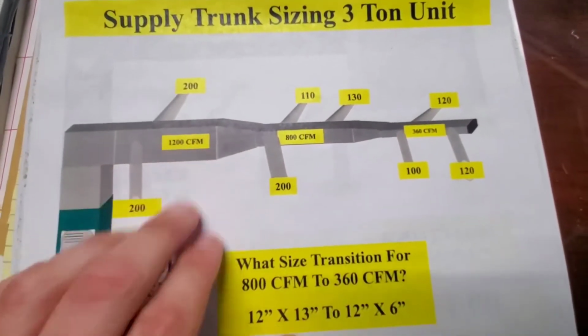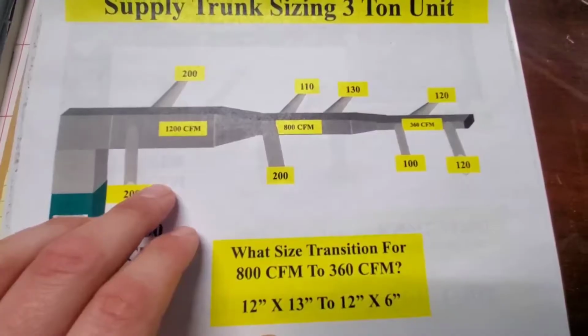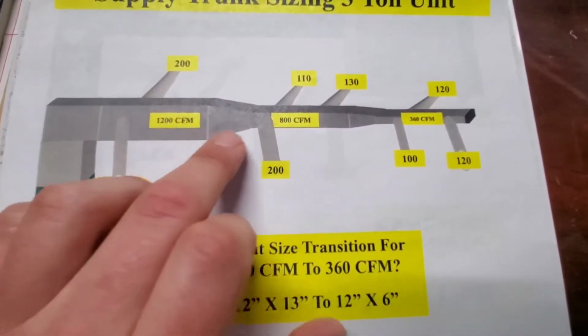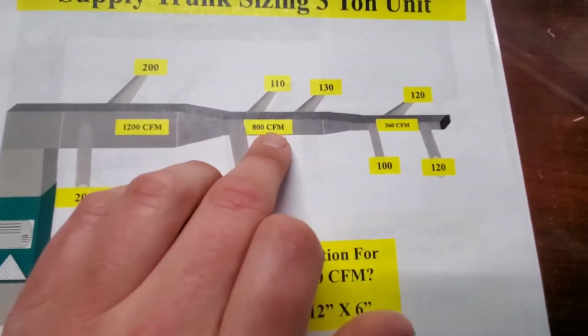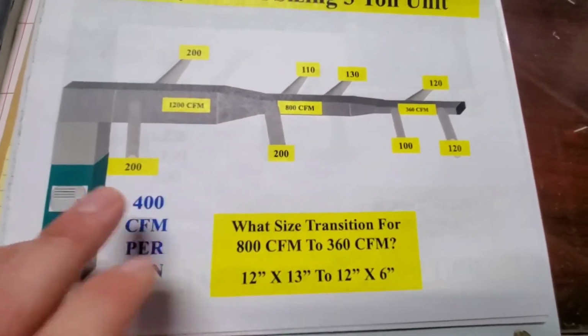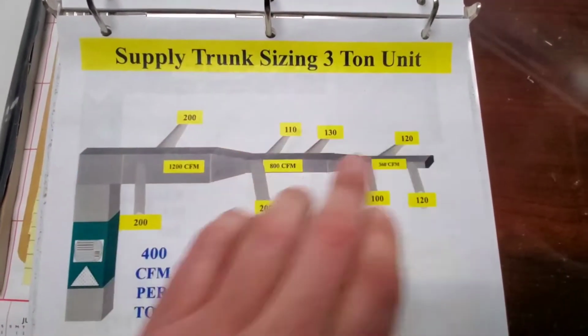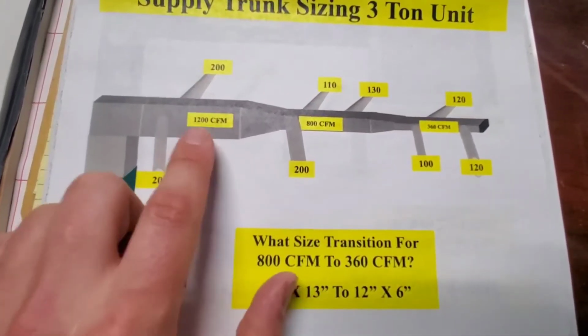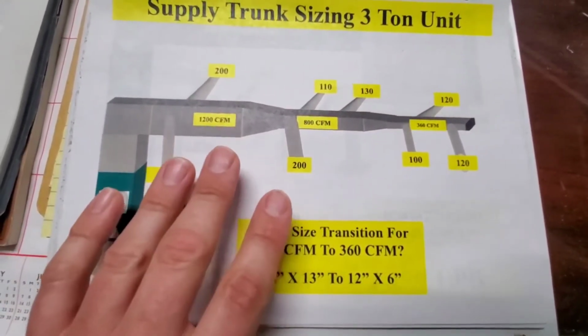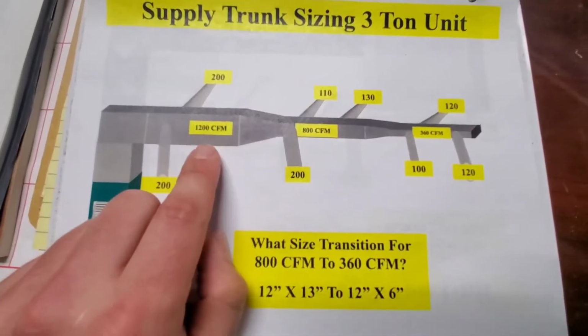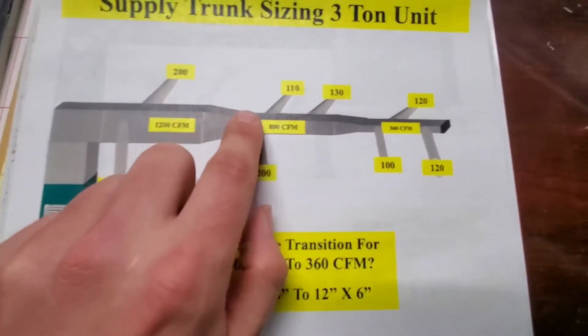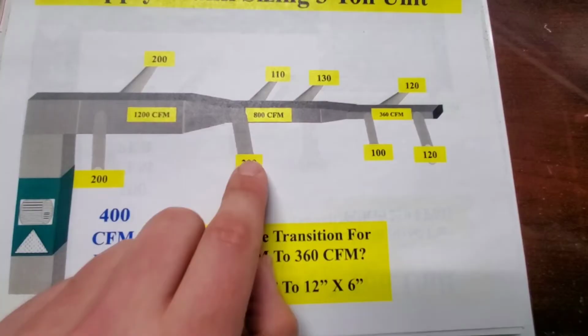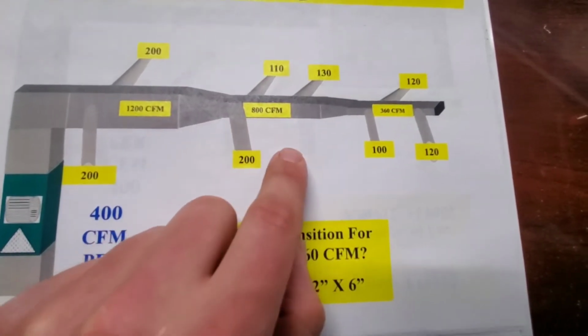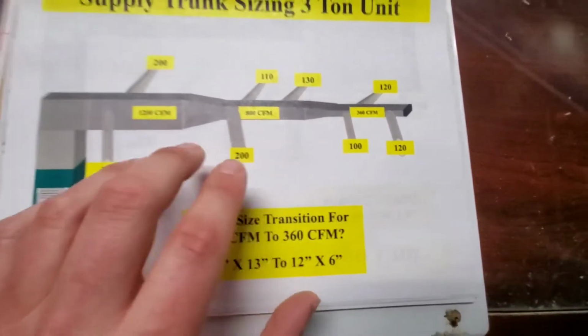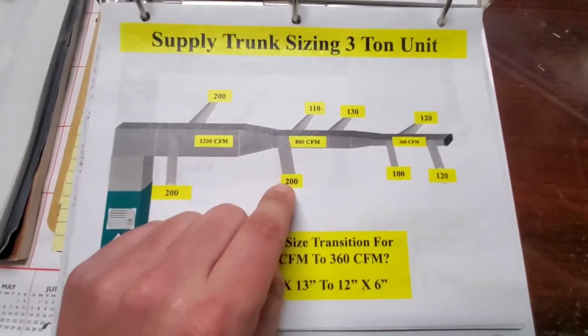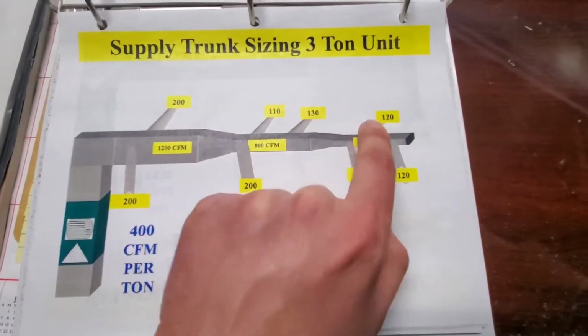So this is 1200 CFM. We take 400 CFM because we've got probably two 8-inch lines, and then we size it down, and then we've only got 800 left. So we started out with a 3-ton unit. See, this is supply trunk sizing for a 3-ton unit. We had 1200 starting out because 400 CFM per ton times 3 is 1200. And then we used 400, and then we sized down 110, 130, 200. So that's equaling out to another 400. And then we size it down again. This is what's going to provide you with an equal amount of feet per minute out of every supply vent.